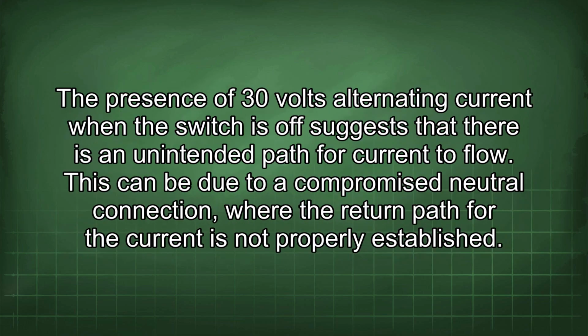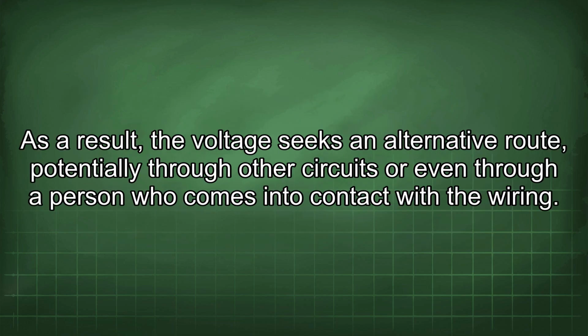The presence of 30 volts alternating current when the switch is off suggests that there is an unintended path for current to flow. This can be due to a compromised neutral connection, where the return path for the current is not properly established. As a result, the voltage seeks an alternative route, potentially through other circuits or even through a person who comes into contact with the wiring.